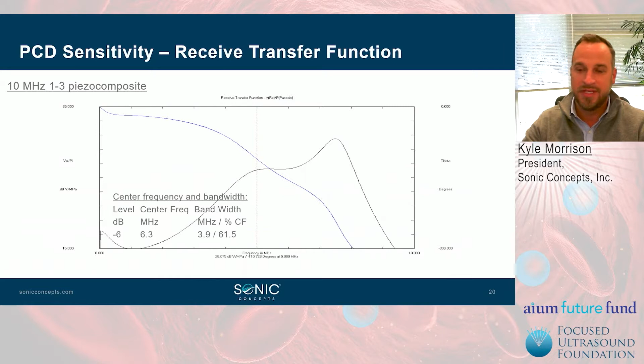Just to finish, we have a couple of other designs that are not ultrasound guided and integrated with focused ultrasound. On the bottom left is a two-way side-looking PVDF sensor that you can actually put near an invasive probe. And on the top there is a ring PCD. So if you're looking for cavitation events, you can put this ring PCD around the site of interest. And the smaller PCD you get, the less signal to noise ratio you have, the less sensitivity.